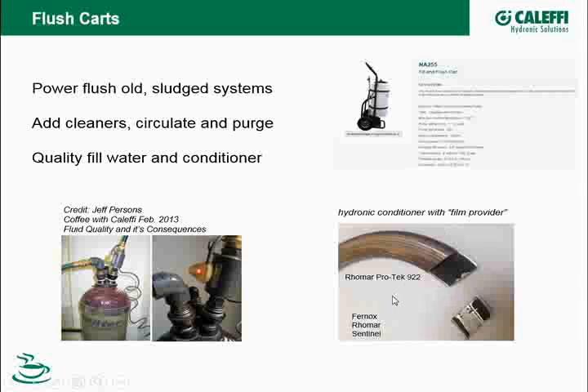Over here on the lower right-hand side, this is actually a heat exchanger that I cut apart that I took out of my own house. It was one of the little ModCon boiler type of heat exchangers, a circular type of heat exchanger. And when I put that in, I did put a cleaner, and then I put a corrosion inhibitor. I happen to use the Rhomar brand, which they call Pro-Tek 955, or 922, sorry. The other one's a cleaner.